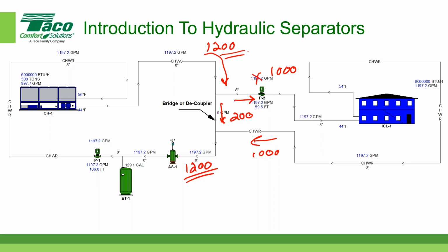And one gentleman is asking, would it be possible to vary the flow in the primary when this case occurs? So instead of it being 1,200, can you slow it down to 1,000? Oh, that's a great question. We're going to cover that in a few minutes. But in this case, remember, we're not going to slow down the primary at all. We're just going to say that the primary is constant flow. Whenever we vary the primary flow, that's a different phenomenon. So in a classic primary secondary circuit, the primary flow is constant.